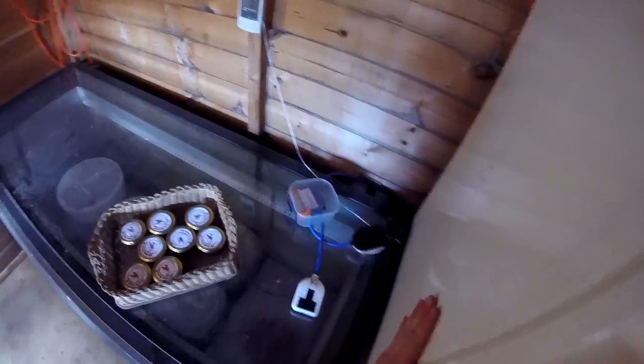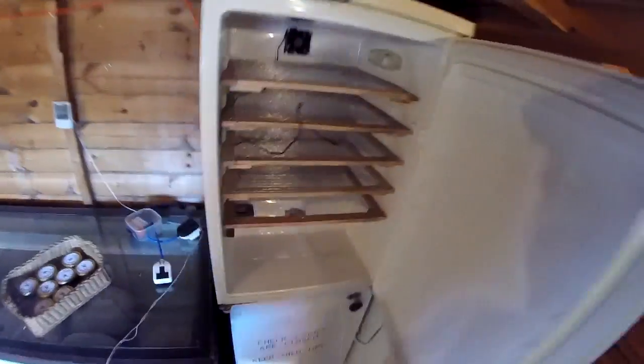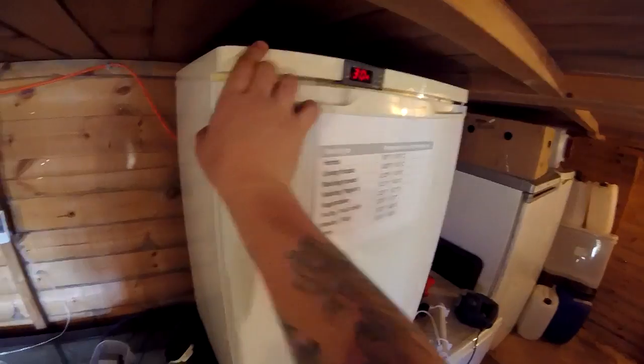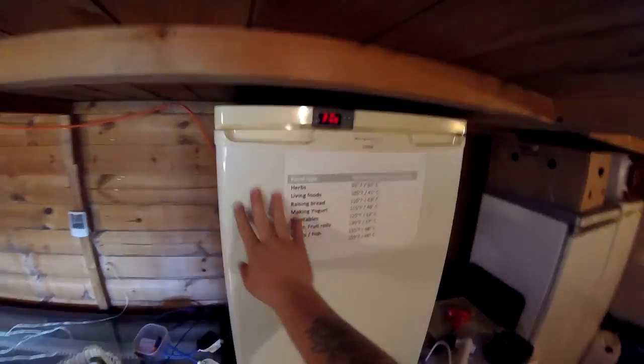I know you might think 'oh my god', but just remember: when the unit gets to 68 degrees the STC cuts it out anyway, so we're not going to reach 200 degrees and risk a fire. It will be supervised at all times. Moving the STC out of the way, getting the unit back in position and plugging her back in — you can hear it running. Using that hair dryer it really does get up to 68 degrees in no time at all.